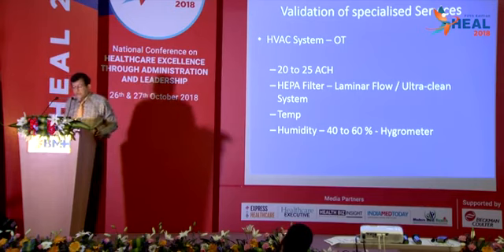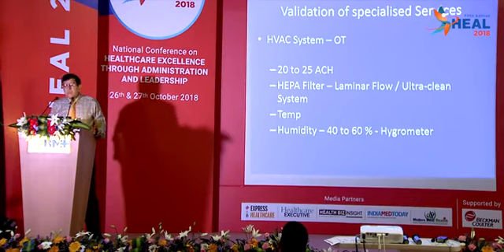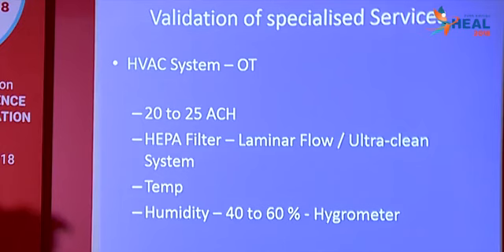Another important aspect is that we can validate the specialized services. For example, the HVAC system of an operation theatre. We can check while sitting in the office whether it is providing 20 to 25 air changes per hour, whether the filters are working, what is the temperature, what is the humidity. So all that we can validate while sitting in the office.